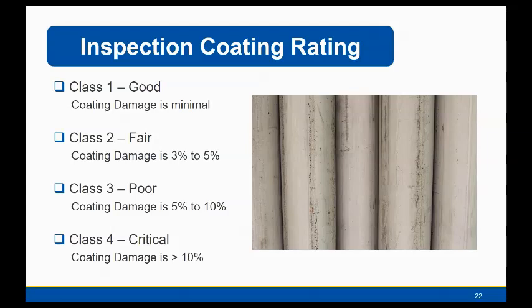In this case, I'm almost certain they're talking about surface area, but that's something that you would want to call out or be a little bit more specific where you can to say, you know, this measurement. For any kind of metal loss or corrosion, you can actually go out there with the pitting gauge or a ruler and actually measure these out and show what it is in comparison so that these percentages actually mean a little bit more.